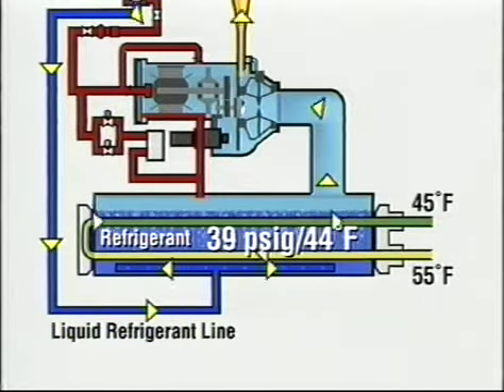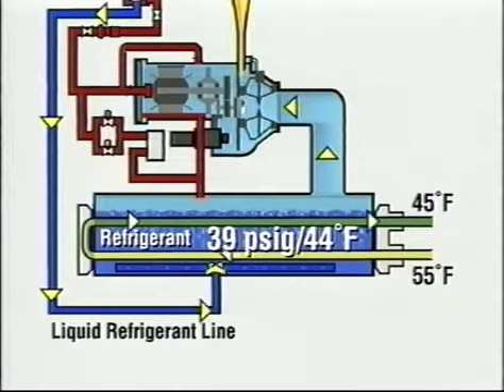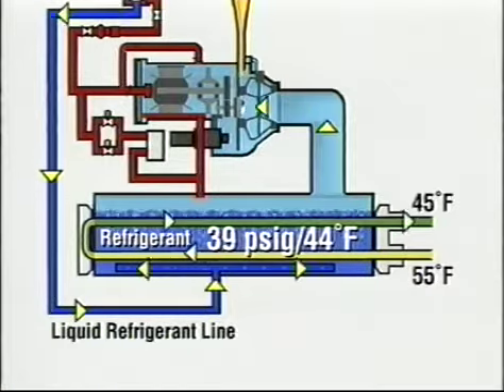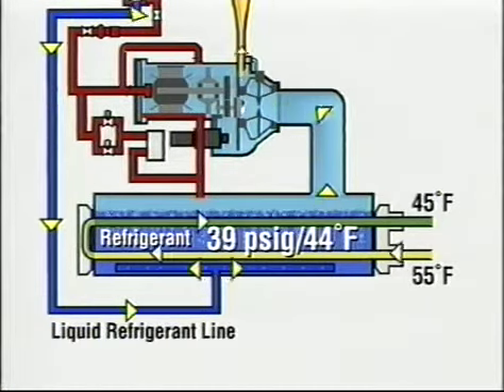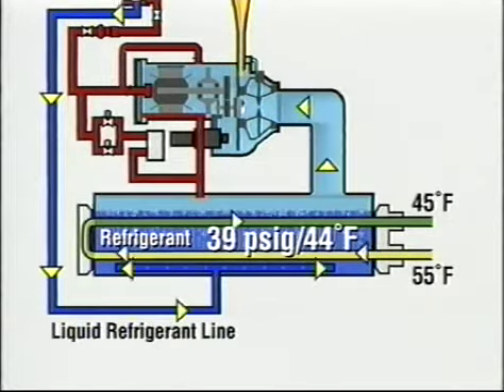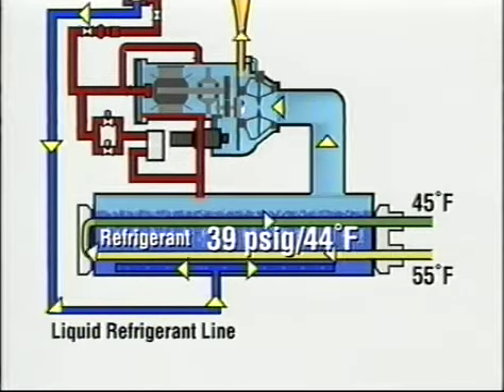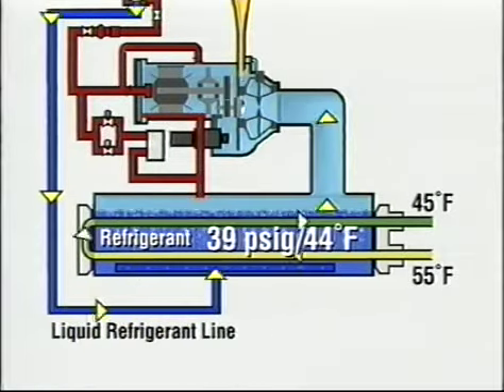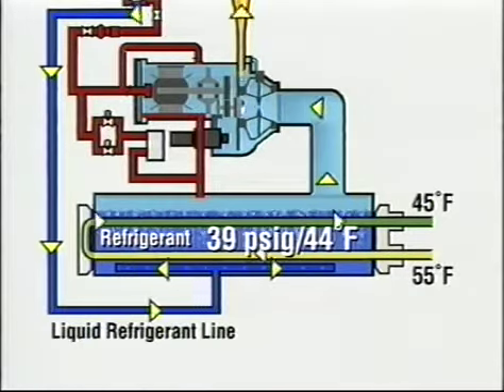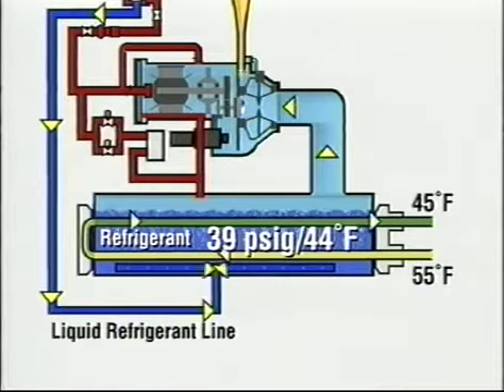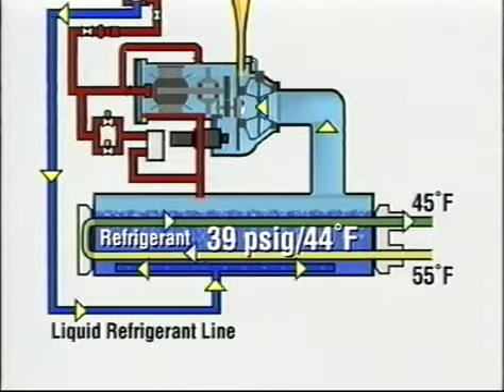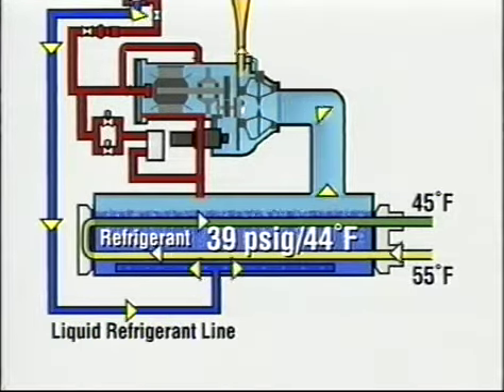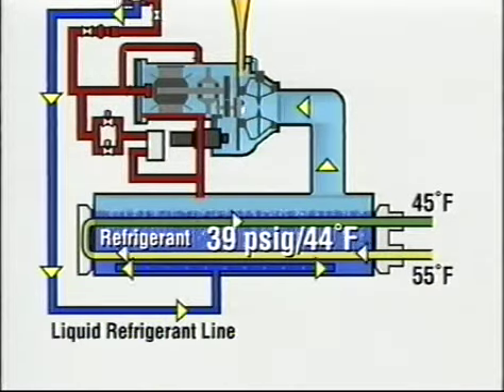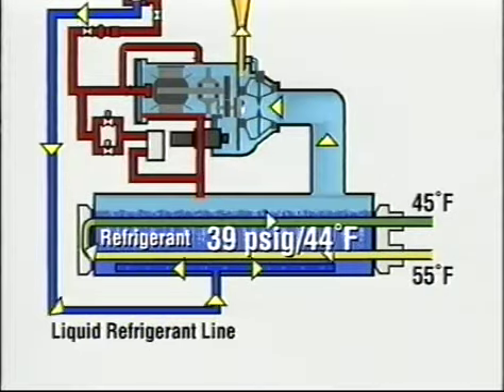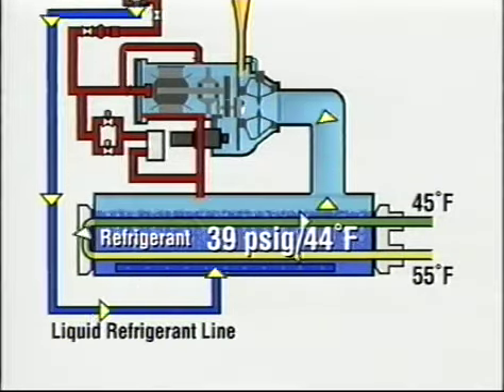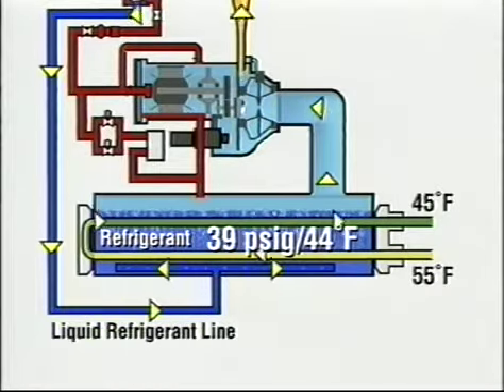The centrifugal compressor continuously draws refrigerant vapor from the evaporator, or cooler, maintaining the evaporator pressure at 39.0 psig, which corresponds to a saturated evaporation temperature of 44 degrees Fahrenheit. The 44-degree liquid refrigerant picks up heat from the chilled water flowing through the tubes, causing the refrigerant to evaporate and cooling the chilled water from 55 degrees Fahrenheit to 45 degrees. The entering chilled water temperature is not controlled by the chiller. It is the air handlers or load supply that will send out the water at a temperature that's based on the load in the building. The 55-degree Fahrenheit temperature is the full load entering water temperature that the machine will be able to pull down to 45 degrees Fahrenheit at the designed condenser water temperature. The chilled water is distributed to fan coils which cool, dehumidify, and filter the indoor air.